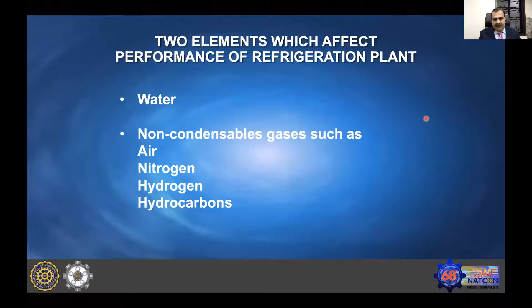First, let's see what happens with non-condensables, particularly air, when it comes into the refrigeration plant. Typically, ammonia gas at 35 degrees centigrade and 13.5 kg per centimeter square pressure should condense from gas to liquid when heat is removed using air or water. But at the same pressure, nitrogen needs to be at minus 164 degrees centigrade to liquefy. So if nitrogen is present in our system, it will remain in a gaseous state. The same happens with air or other gases, which we call non-condensable gases.